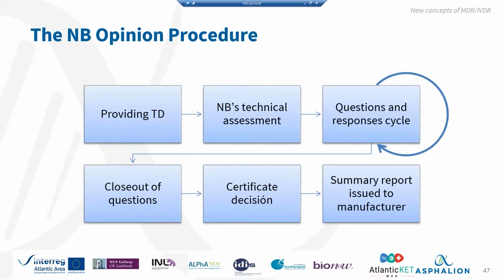And once all these questions have been closed out, the notified body will issue a certificate decision. In this certificate decision, they will indicate if the device complies or not with the regulation. This will all be written down in a summary report, which will be issued to the manufacturer.